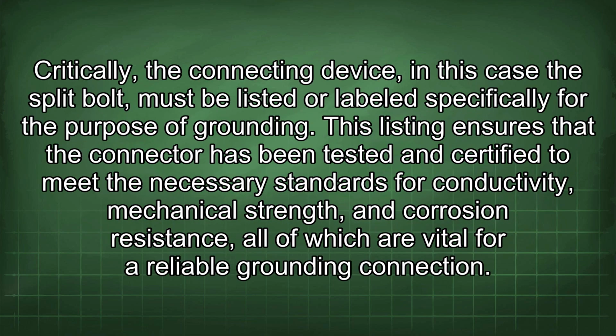Critically, the connecting device, in this case the split bolt, must be listed or labeled specifically for the purpose of grounding. This listing ensures that the connector has been tested and certified to meet the necessary standards for conductivity, mechanical strength, and corrosion resistance, all of which are vital for a reliable grounding connection.